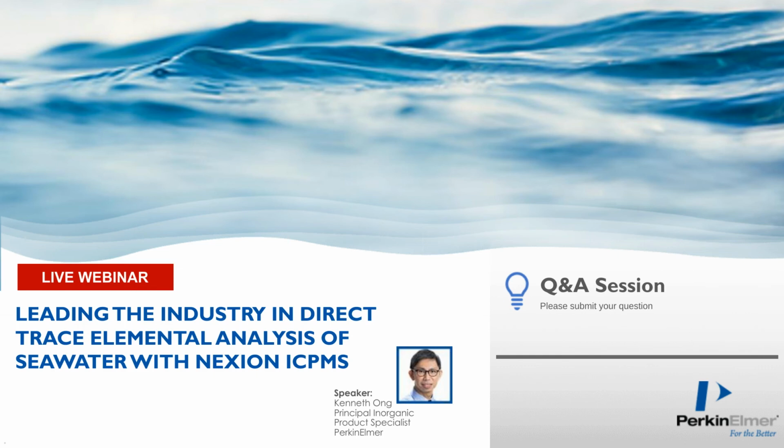Oh, yeah, it depends on the type of ICP-MS that you have. If you are looking at just collision systems, as I just mentioned for the collision cell, if you were to analyze systems wherein your interference is as big as your analytes, then you need to flow a high collision gas, and that will result in lower sensitivity.